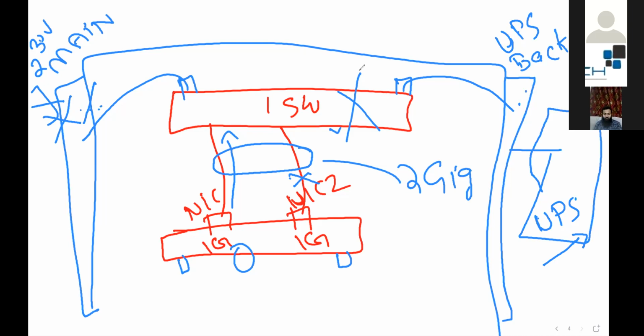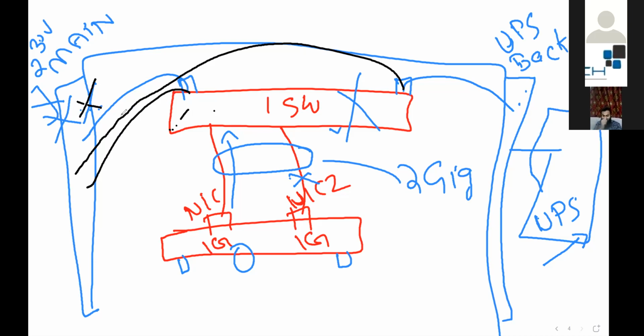If you have two UPS and you connect both into the same PDU, your switch gets more power while the PDU is up. But when that PDU goes down, your switch goes down, irrespective of whether you connected two or one. Whenever you have an extra power or extra connection for any device, you have to think about the proper design.